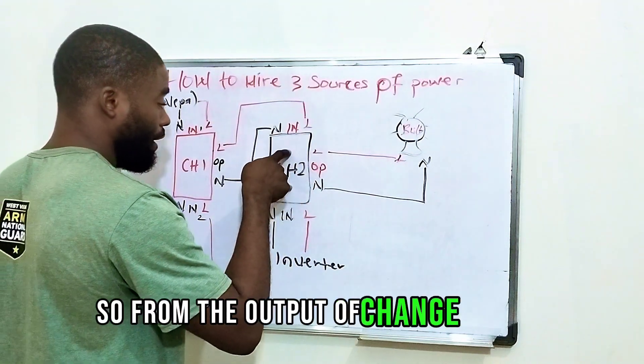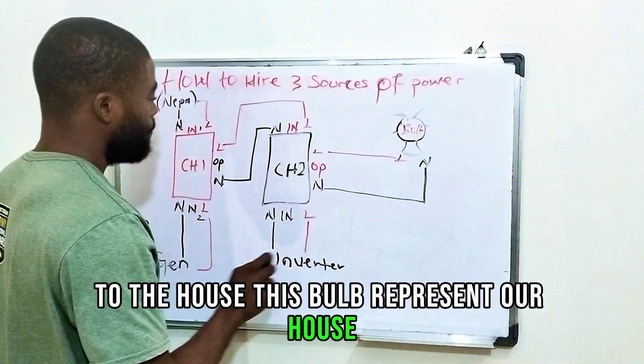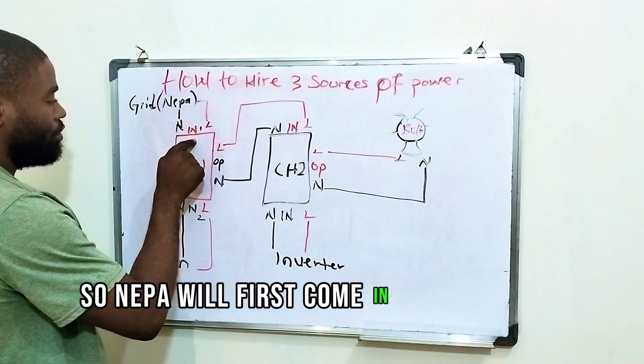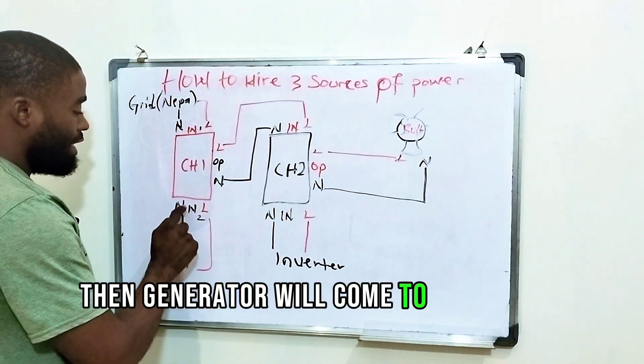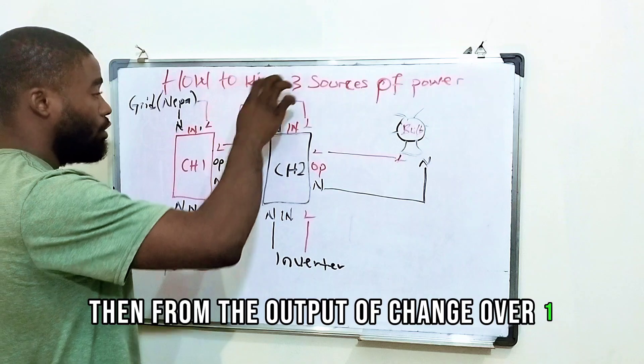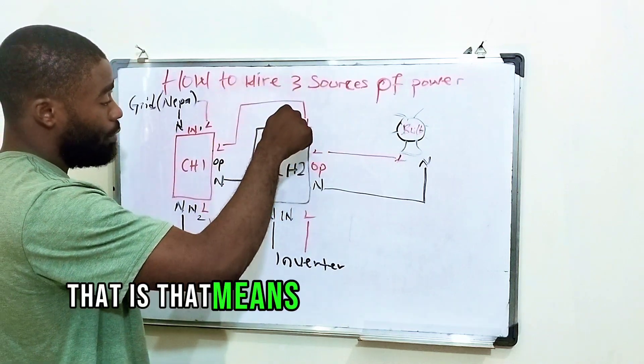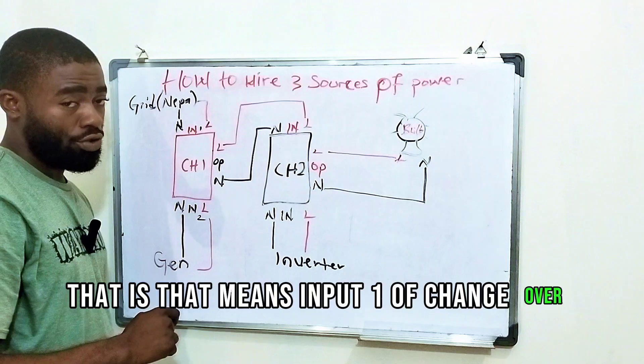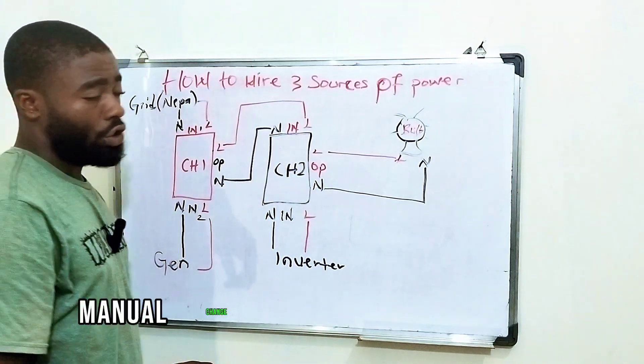So from the output of changeover two to the house. This bulb represents our house. So NEPA will first come in to the input one of changeover one. Then generator will come to the input two of changeover one. Then from the output of changeover one to the input one of changeover two. This is how you do your connection using two manual changeovers.